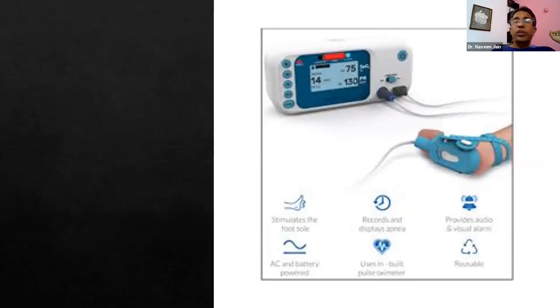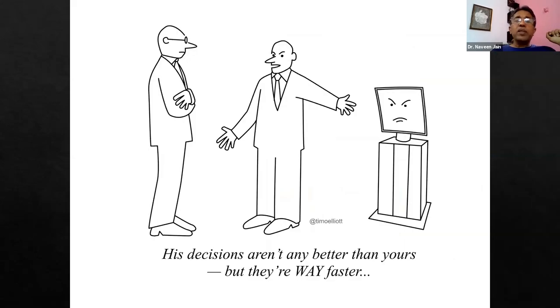Similarly, this is called an apnea boot. We know of pulse oximeters which can pick up apnea in babies by picking up saturation and heart rate. This apnea boot has a very small vibrator also in the device. When the baby's saturation and heartbeat falls, this vibrator simply gives a vibration like a nurse or doctor might have given a stimulation, and the apnea will get aborted. The amount of time the baby spends in hypoxia and bradycardia can be dramatically reduced. There was some role we could play from our institution when this was being developed by Sree Chitra Institute in developing this apnea boot.